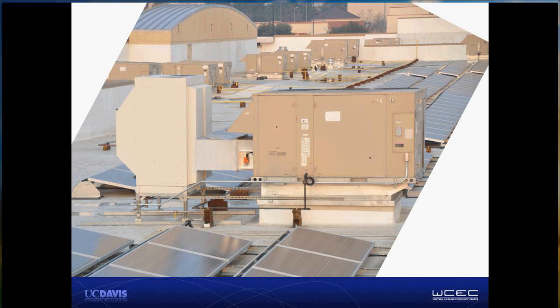UC Davis actually had to develop a custom controller to take all of the 24-volt AC inputs from the building management system and map them over to control the indirect evaporative and the rooftop unit in this combined way that I've described, and to sequence them appropriately so that the indirect evap system has priority when it should have priority, but economizer cooling and ventilation is still supplied when the indirect evap system is off. There are, we think, some simpler ways to do this going forward. I'll discuss those in a little bit more detail later on.